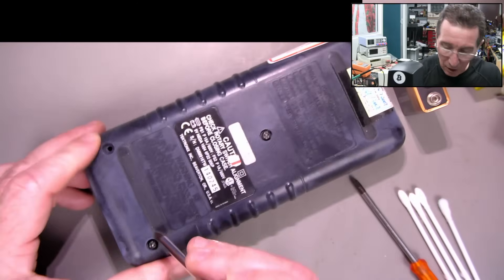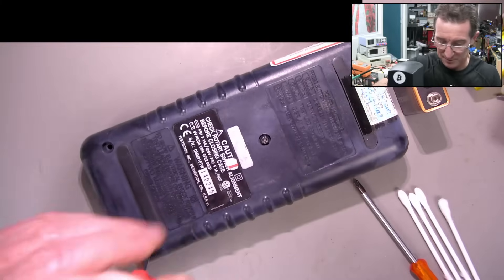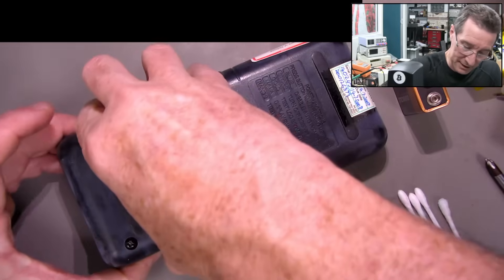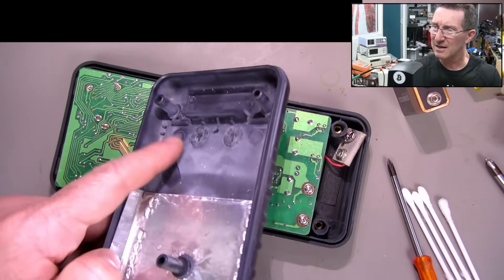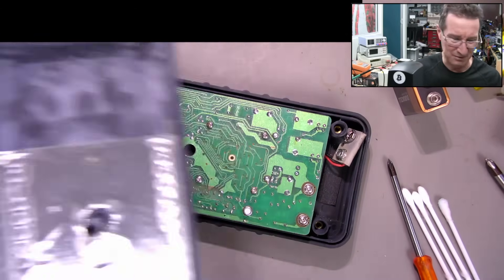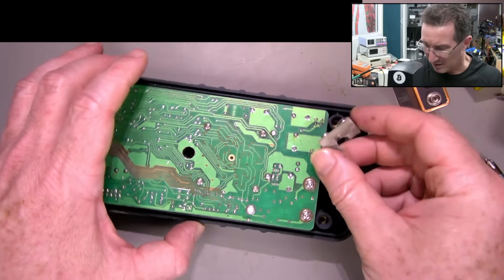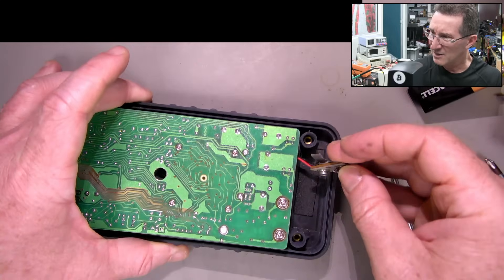These have had a red failed tag on them and somebody cable-tied it. This one was last calibrated 2008 - older than the others. It's discolored in some way. Not sure what kind of life these things have had. One screw missing - don't have a replacement. The battery holder has seen better days.